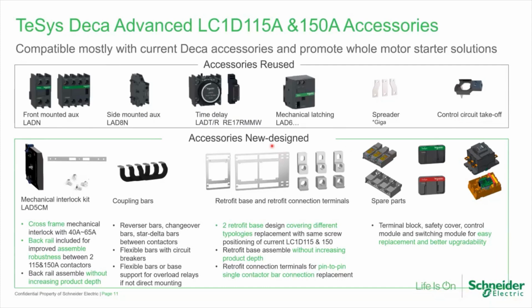However, new accessories have been designed to accommodate many more applications with this contactor. The first one is the mechanical interlock. So the new mechanical interlock is designed, and while we are offering you the mechanical interlock, we are also offering you a rail which will sit on the back of these contactors. This rail will ensure that both the contactors remain intact even if there is vibration or shock. We also offer a lot of coupling busbars. These coupling bars can be used in between circuit breaker and contactor, or contactor and overload relay. If you want to mount the overload relay separately inside your panel, these coupling bars can be used. Similarly, for reversing application or star delta application, you can use ready-made coupling bars which are available with these contactors now.